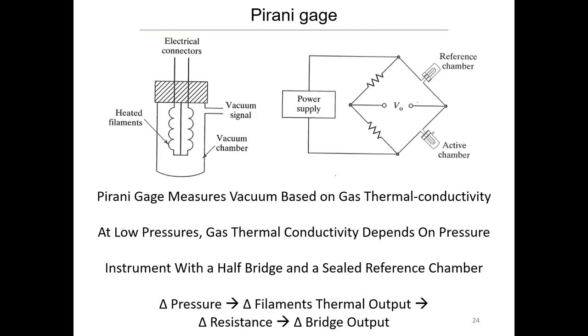One of the more modern devices is the Pirani gauge. It has a heating filament and a chamber where the vacuum is admitted. The change in pressure results in a change in resistance. Because of that, it's placed into a Wheatstone bridge: an active chamber, a reference chamber, two fixed resistors, and then we can measure output voltage with an ADC, which allows for dynamic measurements.